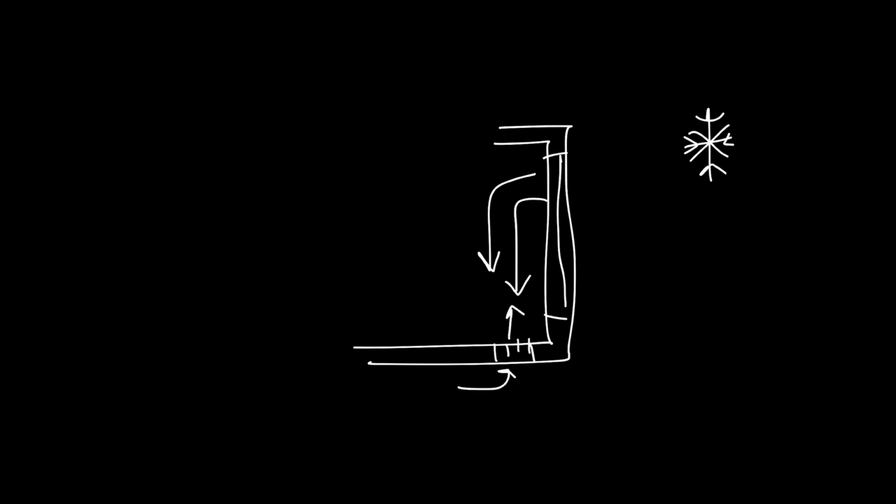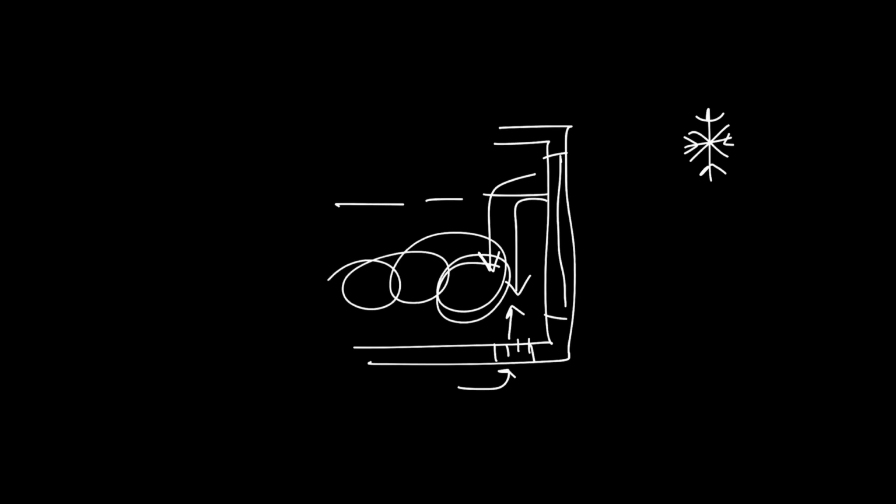Because heated supply air will rise, the most efficient way to accomplish perimeter heating is to supply air from below the floor or sill and use the natural buoyancy of the heated air to cover the perimeter window. Unfortunately, supplying cold air during the summer months from the floor will not efficiently mix the ceiling air where warm air stratifies, and split systems are just too expensive.